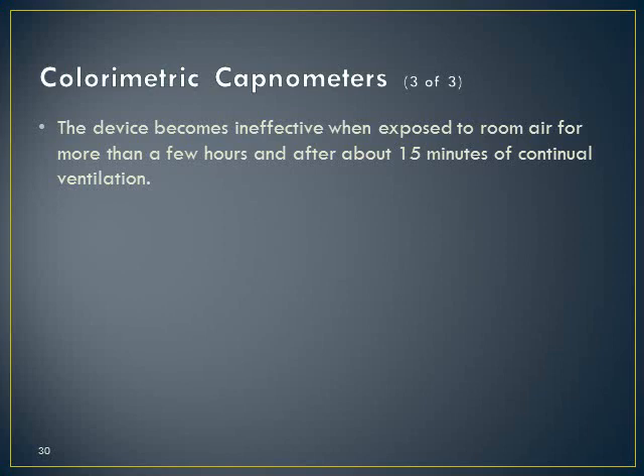It's important to remember that the device becomes ineffective when exposed to room air for more than a few hours, and if we have it hooked up to a patient for 15 minutes, it will continuously change color for about 15 minutes with each breath. We inhale, it'll turn purple. As we exhale, it'll turn gold again, verifying that we're good. But again, if you leave it out for more than a few hours, it's going to lose its effectiveness.